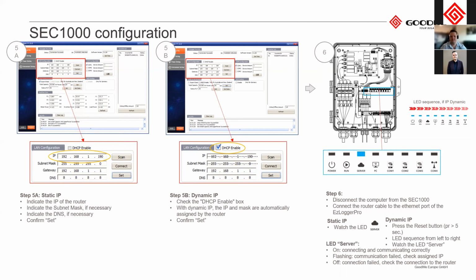Alternatively, you can use DHCP. If you're installing a standalone router just for this, as some sites have high network security, they prefer you just to install an external router, an external 3G router or something like that. You can also just use DHCP, because normally there's only going to be 2 or 3 devices on the network. Then you select DHCP, you press set, unplug the LAN cable from your computer, plug it into your router, and you should see it connect successfully, and you won't have any issues. Under DHCP, you can also connect to that router, use some sort of program to locate what the IP address is, and then connect to it via Promate as well.